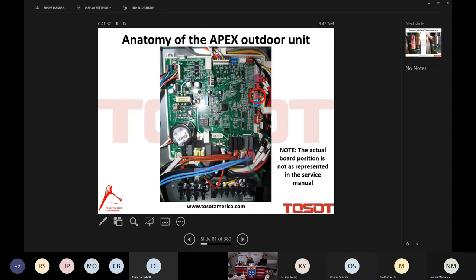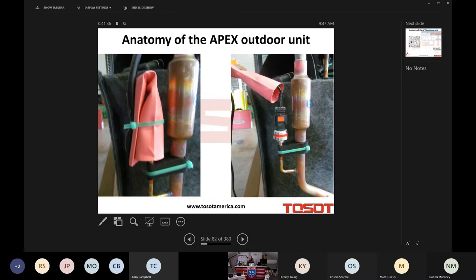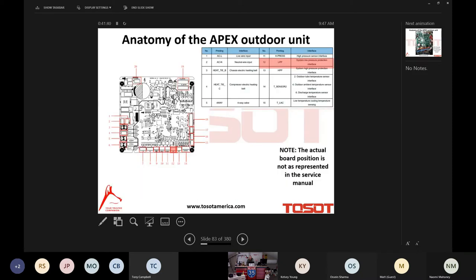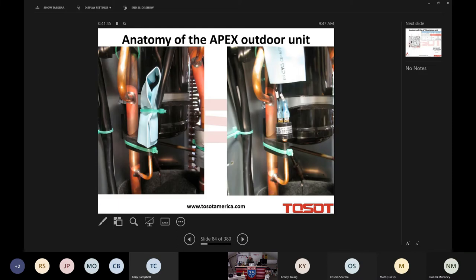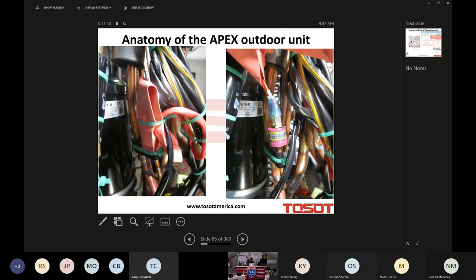So we have a high pressure switch, a high pressure sensor, if you will. Actually, we have two, as you'll see in a moment. Here's the first of the two. And of course, well, maybe not of course, but we do have a low pressure sensor as well in the outdoor unit. And here is that second high pressure sensor. Why two high pressure sensors? Well, for the same reason that we have that electromagnetic interface valve, that bypass valve, because during the heating mode and during the cooling mode, there are sections of the outdoor unit which aren't doing anything, baby, that are completely segregated from the task at hand, so to speak. So that's why there are two high pressure switches, so that each of them are strategically placed that no matter whether we're in the heating or the cooling mode, there is an active high pressure switch in the right place, so to speak. Make sense?